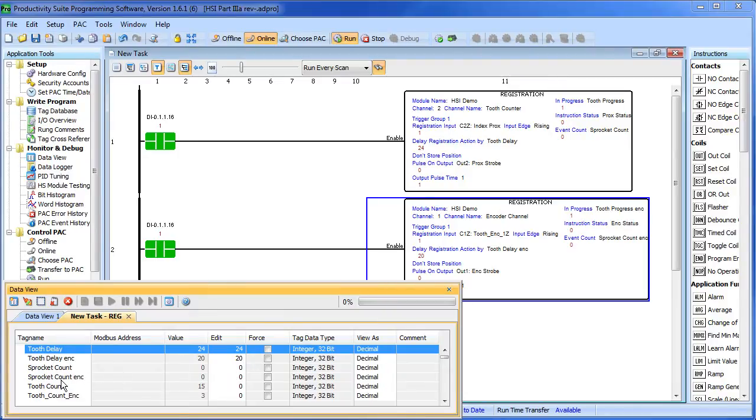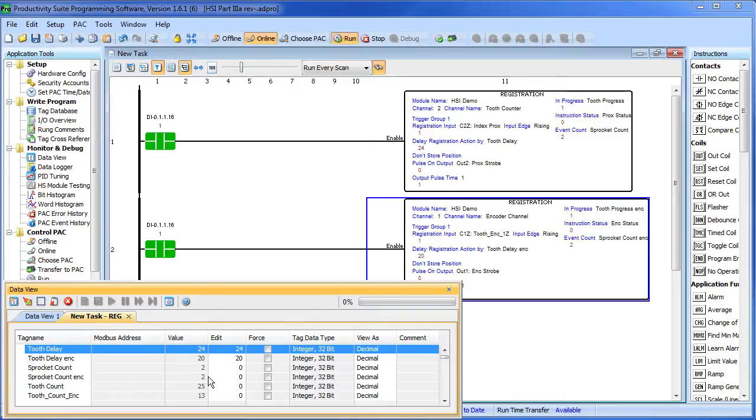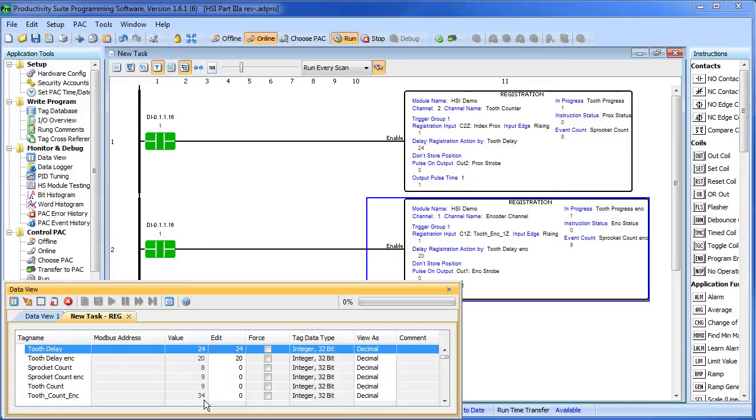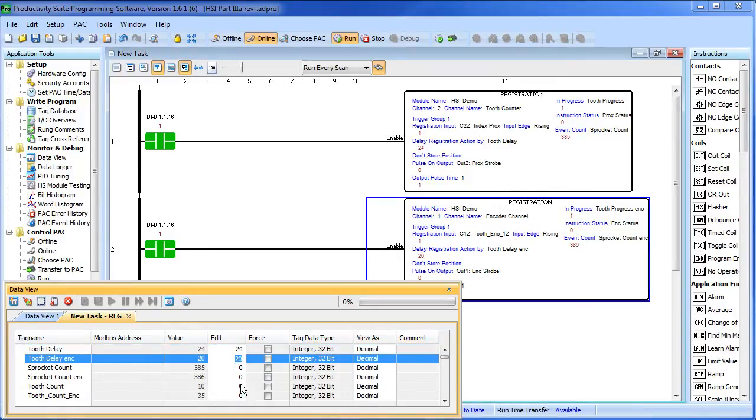Here are my sprocket counts, here are my tooth counts. I'm just going to reach over with my hand and rotate the sprocket some so we can see what's happening. You can see my sprocket rotations are counting and I can see my tooth count when it hits 36 resets back to 0. Perfect. I'm going to change the tooth delay on this encoder to 15 to bring the smiley face around where I can see it.